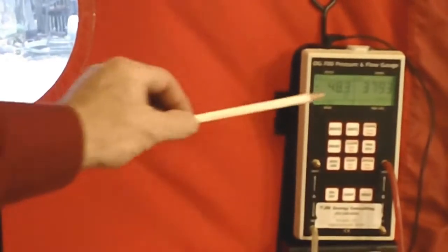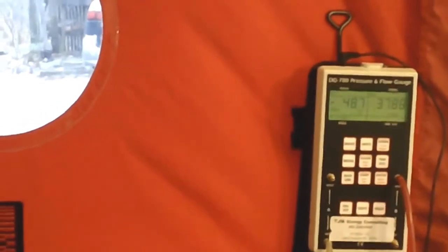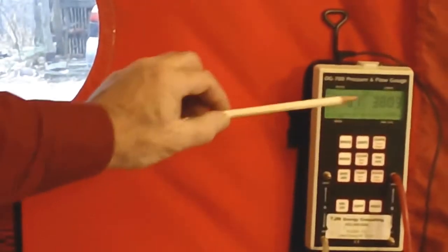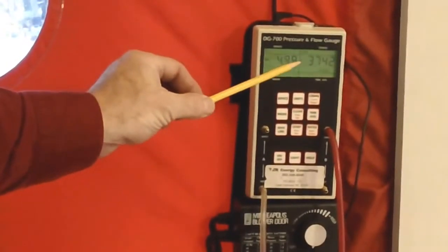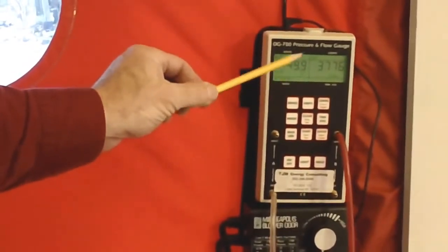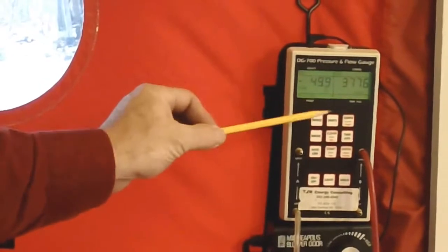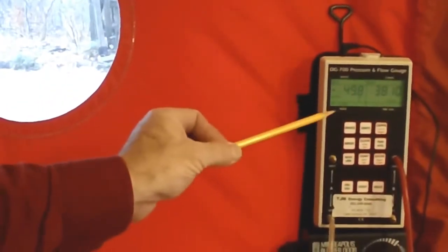So right now, we're looking at a hole that's approximately 380 square inches. It is lower than what we started at. This particular house had a number of about 4,500 cubic feet of air going through it. So this is our final blower door number. Again, we have about 373 square inches of hole in the whole house. We started out with around 4,500, so we're down about 20% in the retrofit. So we did air seal the house. It'll make a difference in their comfort level around the house and their heating and cooling bills.